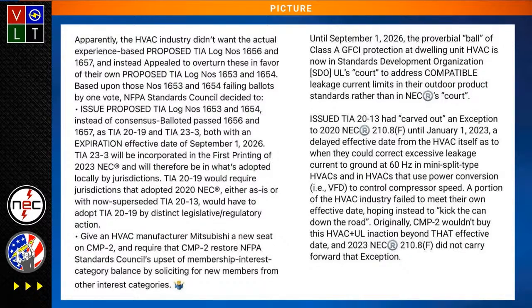So you're looking at putting these GFCI devices on there that have compatibility issues, first of all, that's going to cause tripping. And I brought that up, that the new UL standard that's going to be coming out is at 10 milliamps. It's not compatible with a Class A GFCI device. And they told me I didn't know what I was talking about. All of this is going to be taken care of for the 2023 code. And I said, no, it isn't. I said, y'all don't know what you're talking about. And sure enough, where are we at now? It's not going to happen.